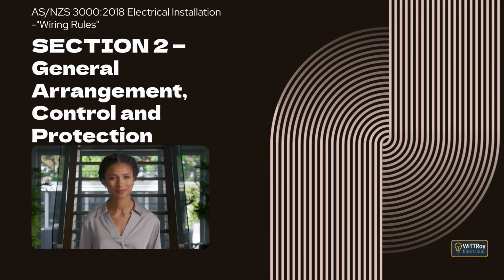Clause 2.10.3.4.2 Location of fuses and circuit breakers. Fuses and circuit breakers must be placed so that their purpose and relationship to each circuit is obvious. They may be installed on the back of a panel or escutcheon only in specific situations, such as when used solely as a fault current limiter or when used for control or instrumentation equipment. Combination fuse switch devices may also be mounted behind a panel if they can still be operated safely from the front.